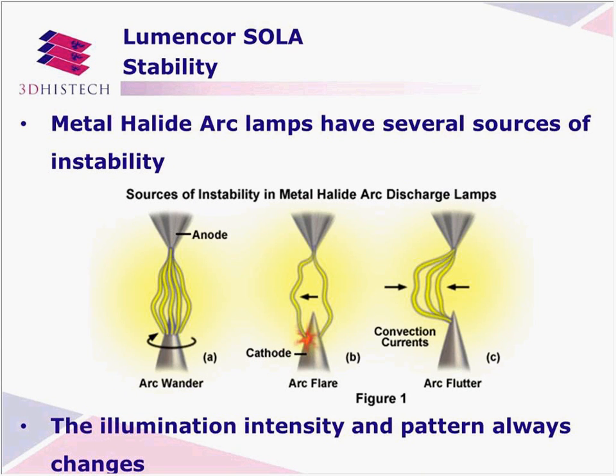So the HXP 120 was using a metal halide arc lamp, but it has several problems, which come from the construction of arc lamps. The first problem is arc wandering. Between the anode and the cathode, the arc is moving. This is called arc wandering, as the arc slowly moves around the electrodes. The other problem is arc flare, the arc actually jumping from one side to the other.